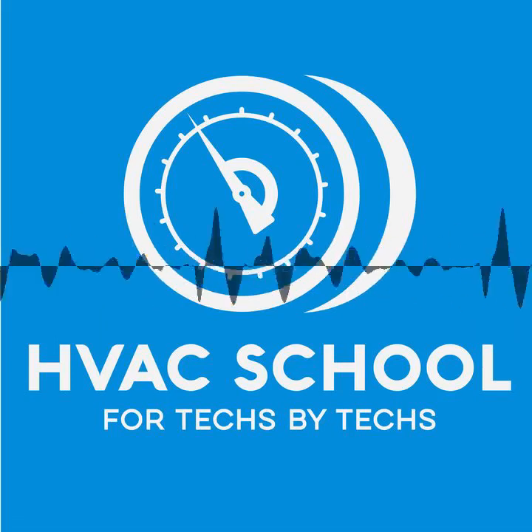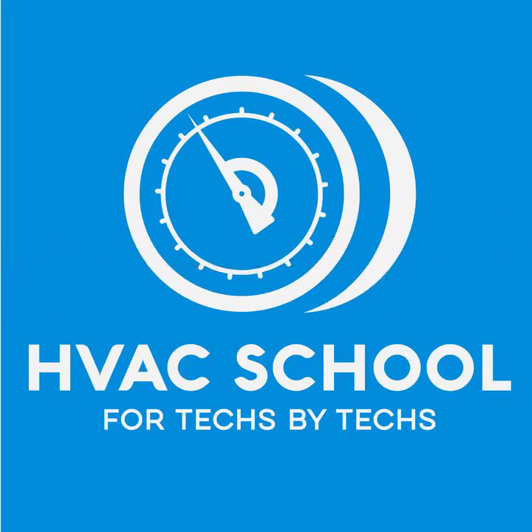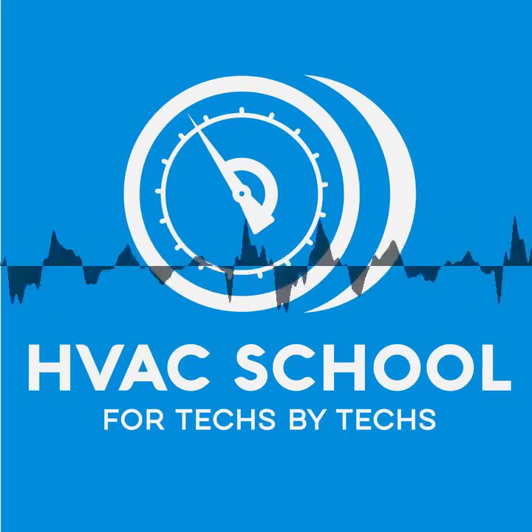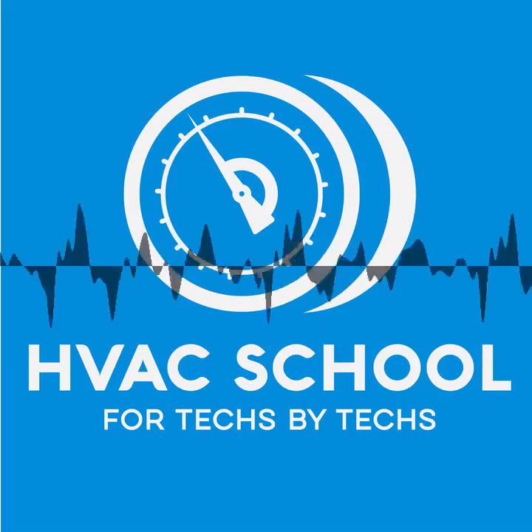I think it's very interesting when you start looking at how this industry works and how the efficiency works. Just because you pull it out of the box and it says it's 97% AFUE on the label doesn't mean it's 97% AFUE as you set it up. That's important to understand. So now we've added in the secondary heat exchanger. We dropped the stack temperature down to below 120 degrees. The only thing coming out of the flue gas now is carbon dioxide, water vapor, and heat energy.